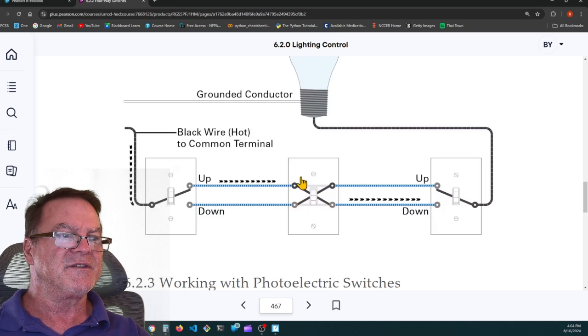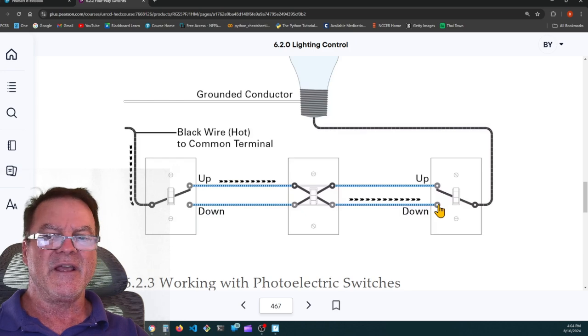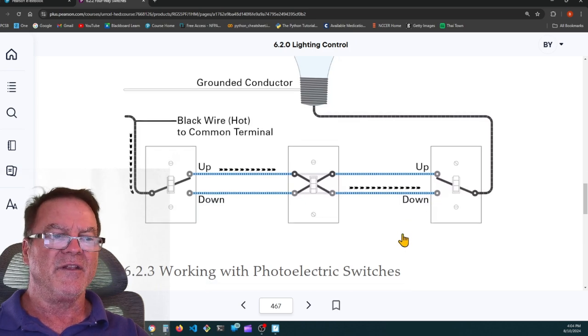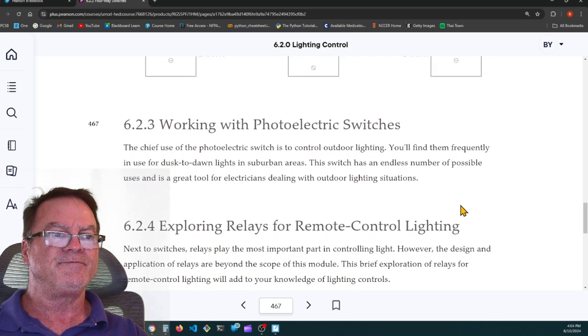Now, in this scenario, they've switched the four-way switch. The two three-way switches are still in their original position, but by crossing the contact bars in the four-way switch, you can see that the potential is going through that contact bar, ending up on the lower traveler, and it dead ends at the lower traveler. The light is not working.